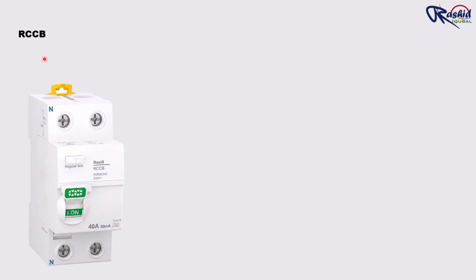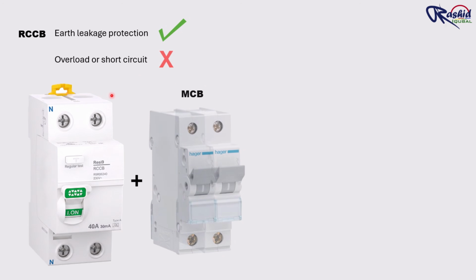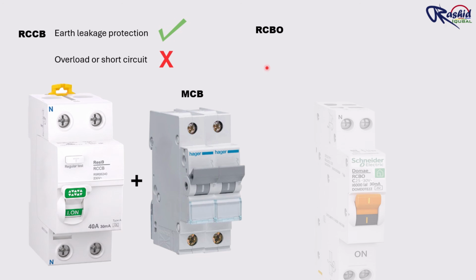Now there is one more important thing to understand. RCCB can protect against earth leakage and electric shock, but it cannot protect against overload or short circuit. Generally we use MCB for overload and short circuit protection. But what if we need both protections in one device? Means RCCB protection plus MCB protection.